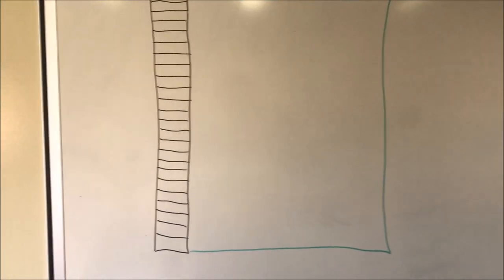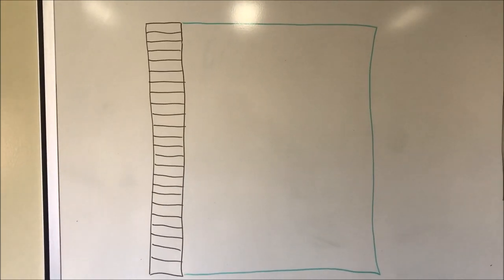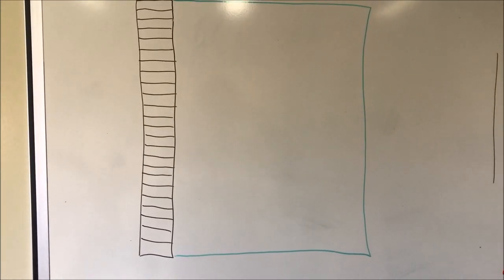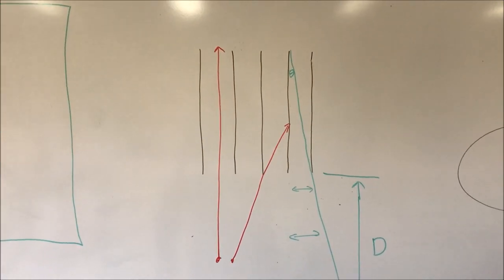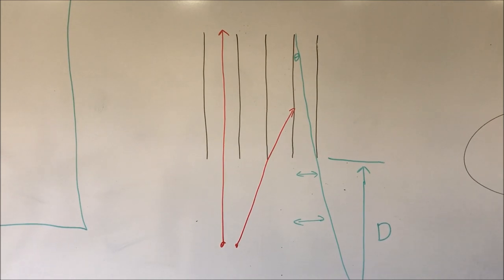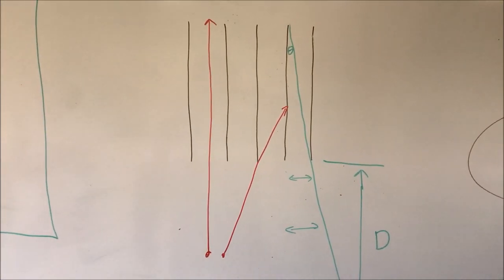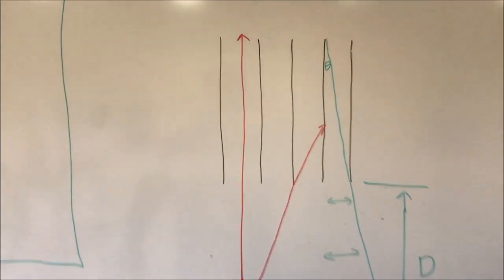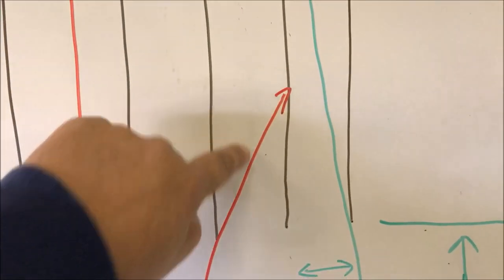We're going to start to build a diagram of the gamma camera horizontally across. You can see we've started to draw in the collimator — this is where the collimator would be on the front end of the detector. The green lines represent the overall detector size. The red lines represent photon emission — if a photon comes in parallel to the septa, it passes through the collimator and will be detected by the crystal. If it comes at an angle, it hits one of the septa and is absorbed by the lead or tungsten.